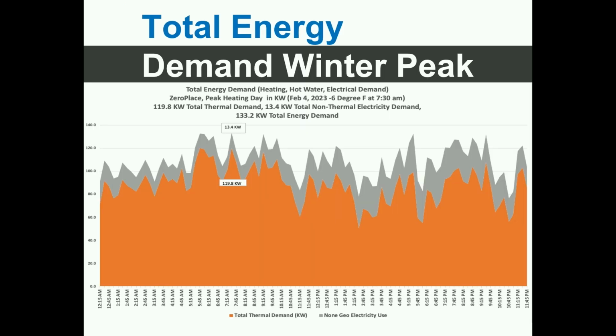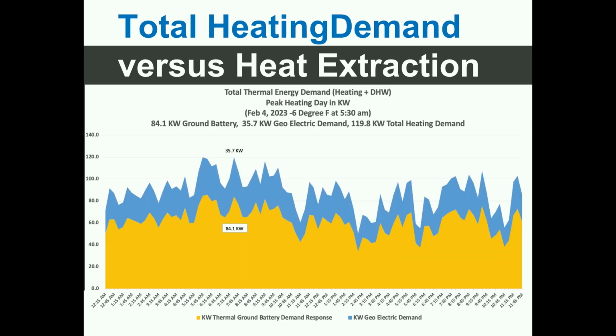And it just shows you here, this was the peak moment I was referring to, where 90% of the entire energy use of the building was thermal energy, and shows you how the thermal energy was fluctuating during the day. But if you now look at how much was delivered by the ground, it shows you that the ground was following that demand and automatically was giving more energy into the building when there was more needed by the heat pumps. So it's almost like a dispatchable battery. It just does it so automatically. And that's really the important part here.